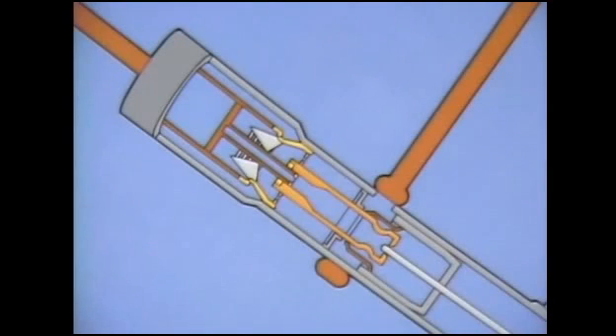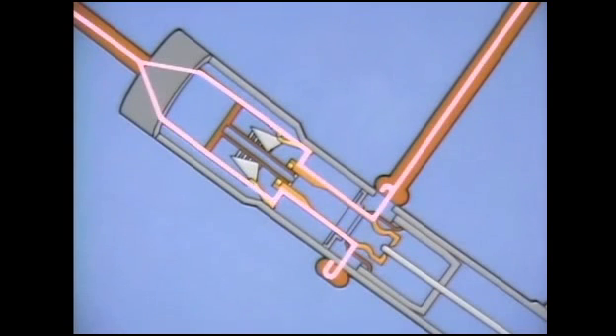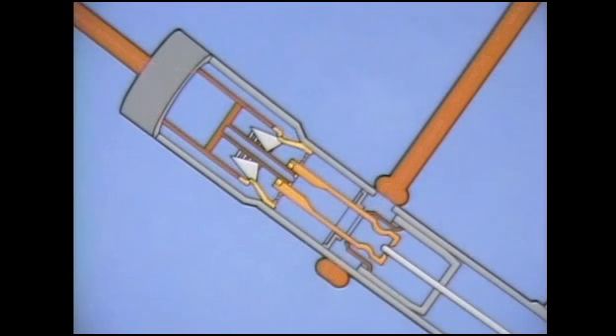In addition to housing the interrupting mechanisms, the insulating tube is filled with SF6 gas at a low pressure. When the breaker is closed, the current path is through the stationary contact assembly and the main contact fingers.